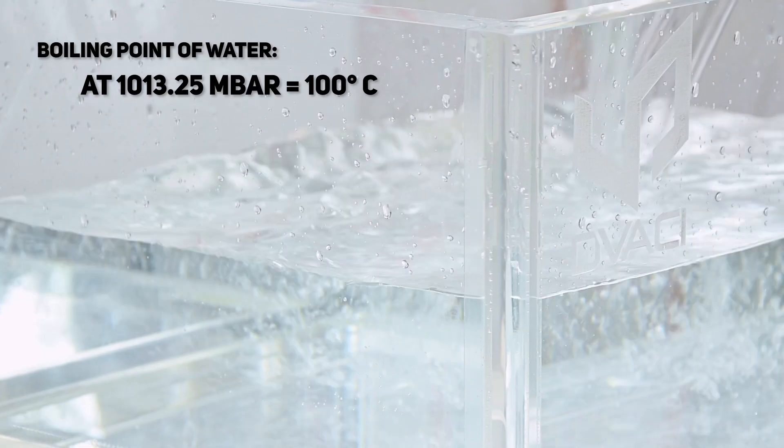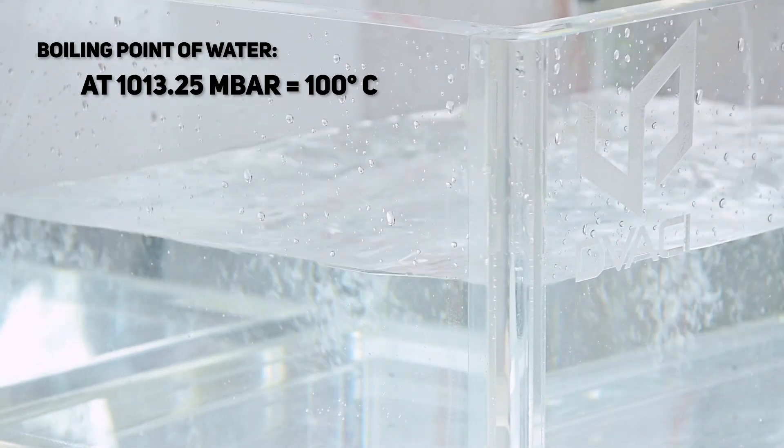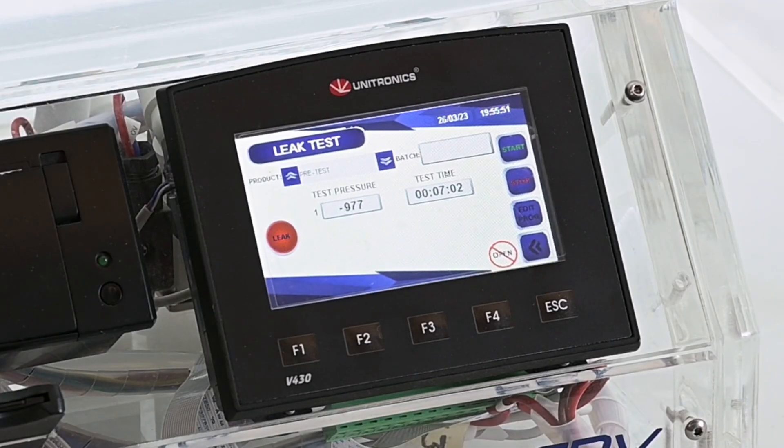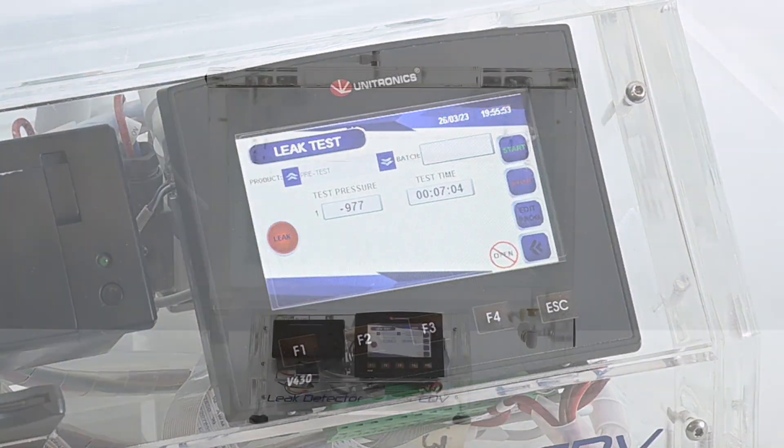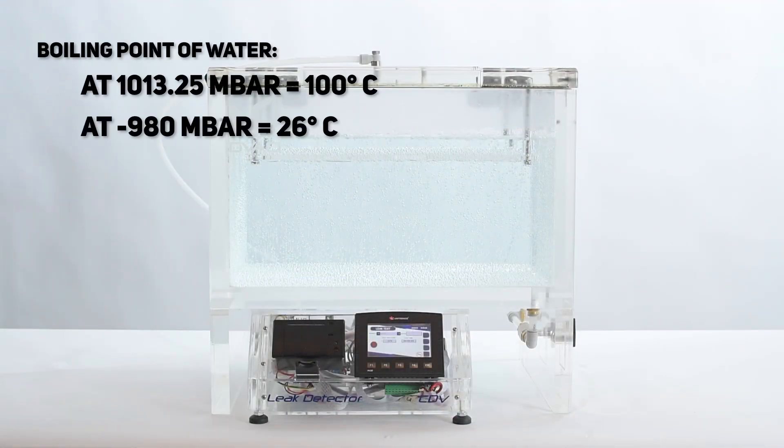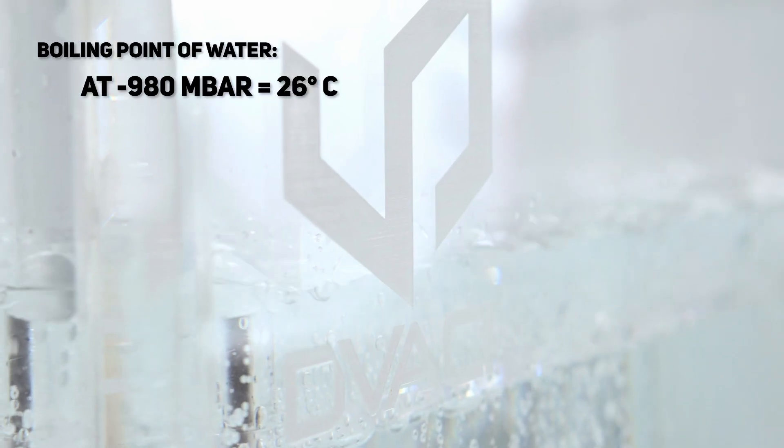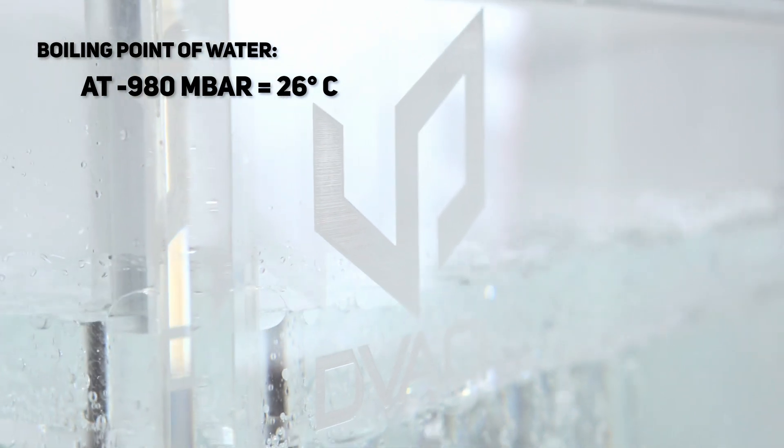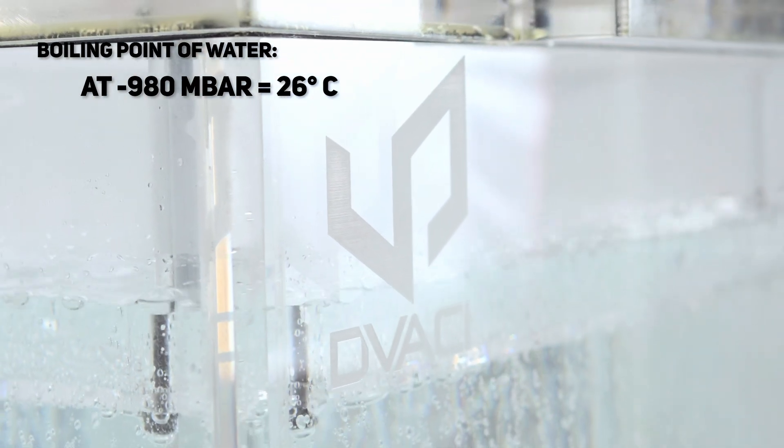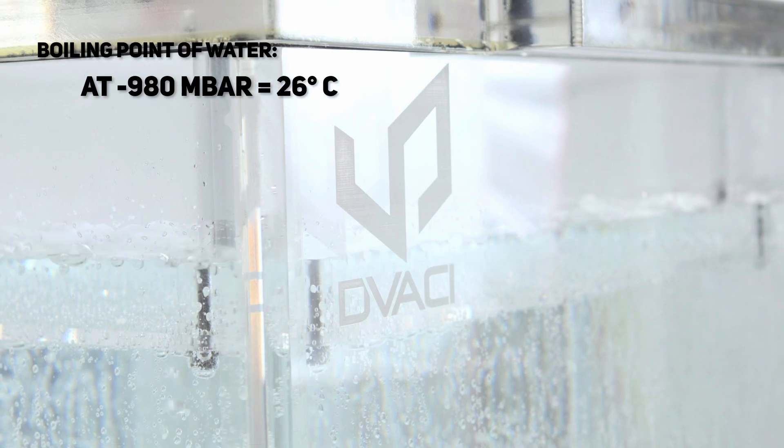Did you know that normal water evaporates at 100 degrees Celsius at sea level, but under minus 980 millibar of vacuum, the boiling point is reduced to about 26 degrees Celsius. At this point, at room temperature, air bubbles will appear, making it difficult to spot a leak during any submersion test.